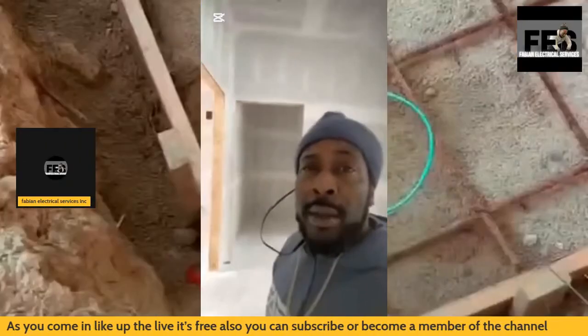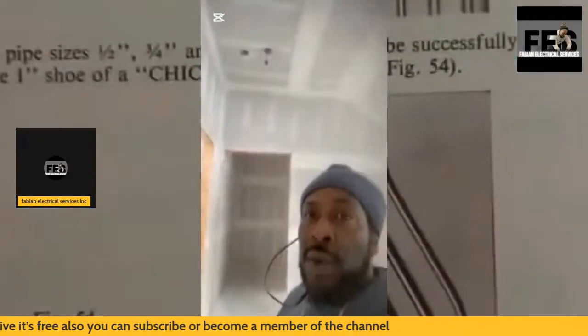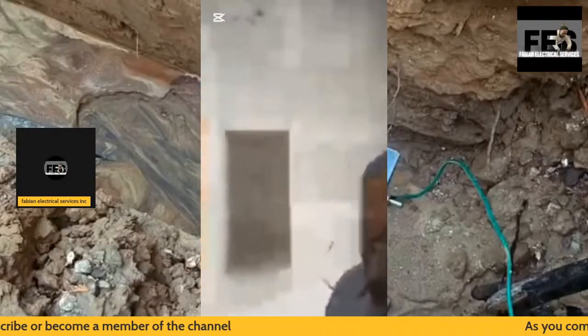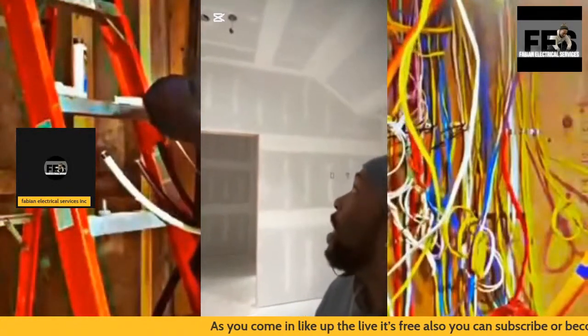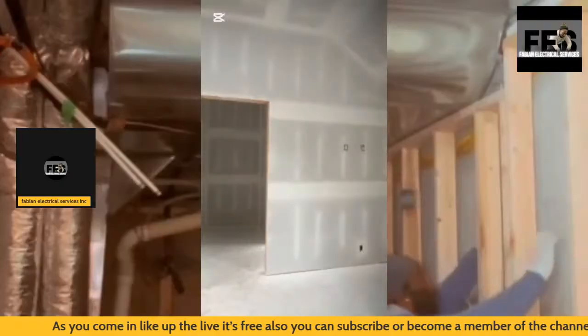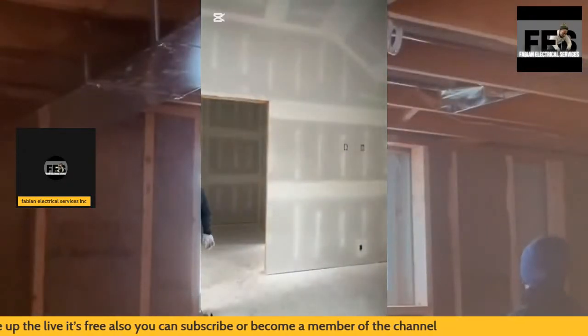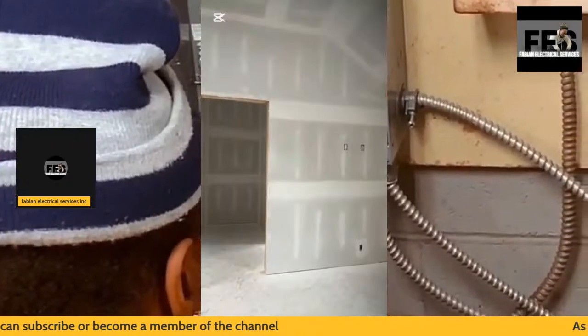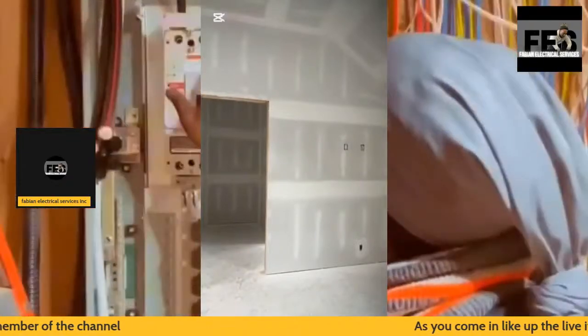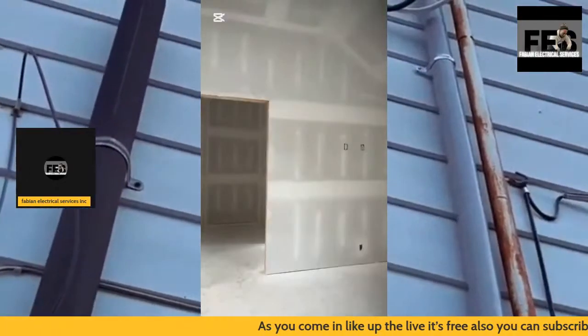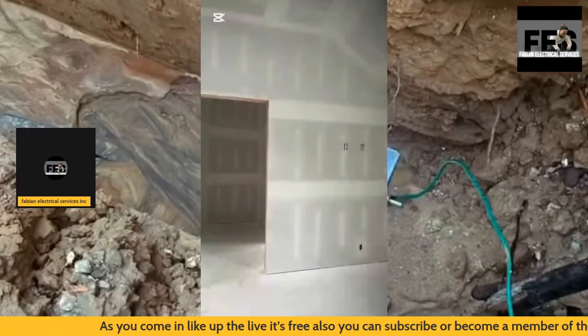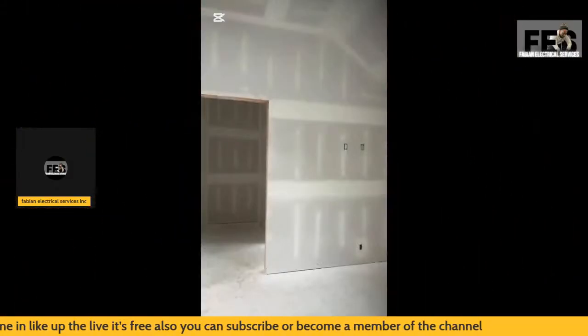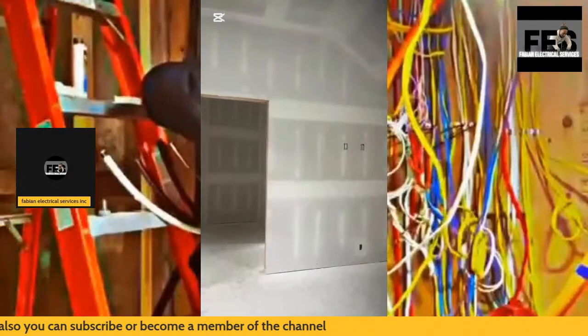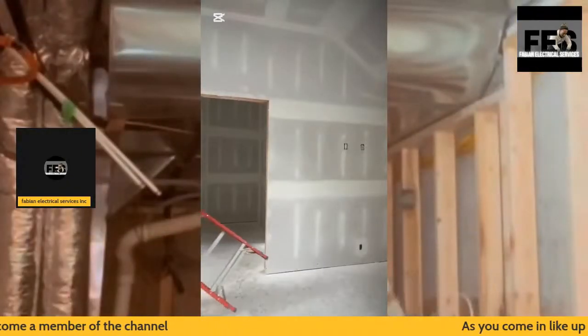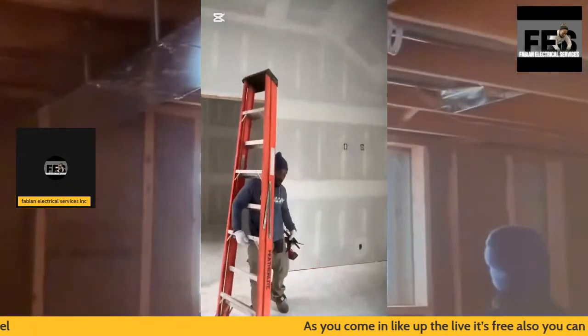So when it comes to lighting, how I like to go about my electrical installation is to simply do a couple of lighting circuits on each floor. That way, if there happens to be an outage of some sort, or the panel loses power on half of one side, the other lighting circuits can still be livened up and continue to work. For this reason, I always make sure I have more than one lighting circuit on the floors.